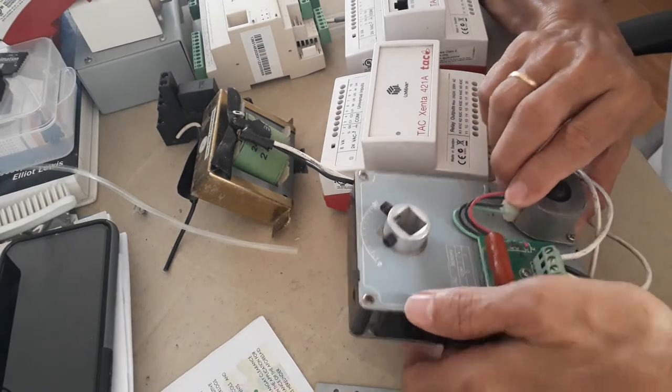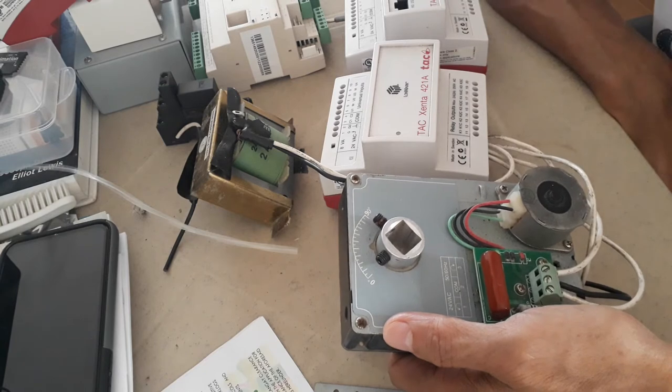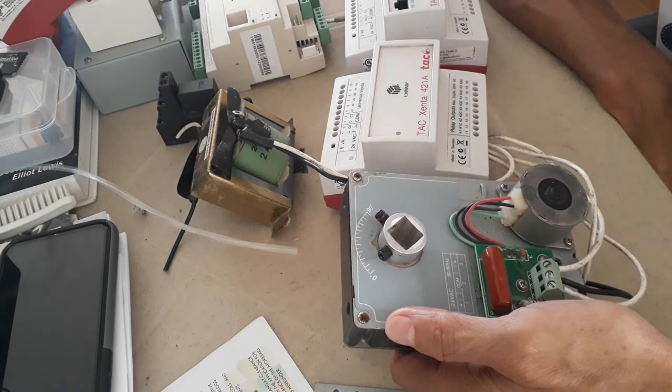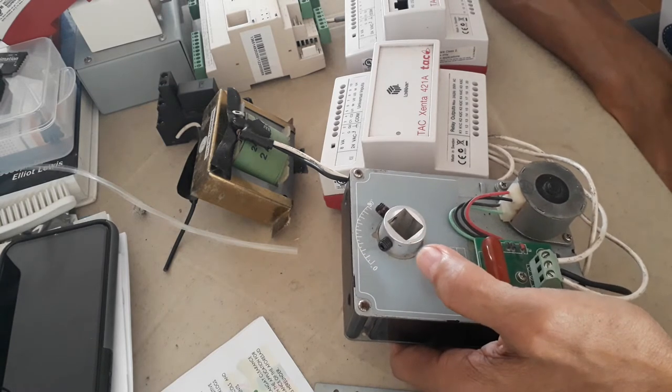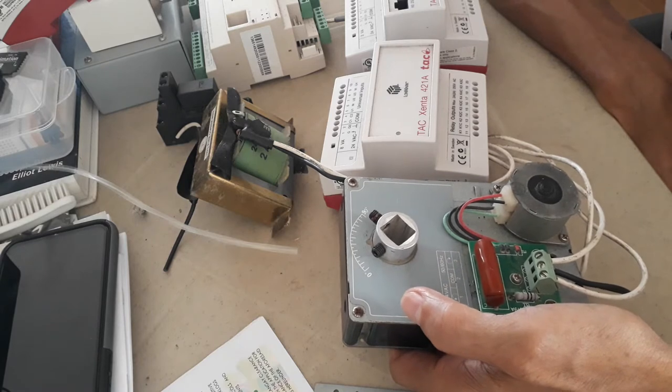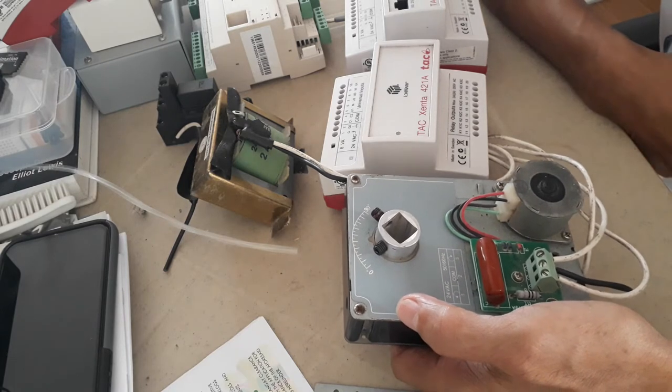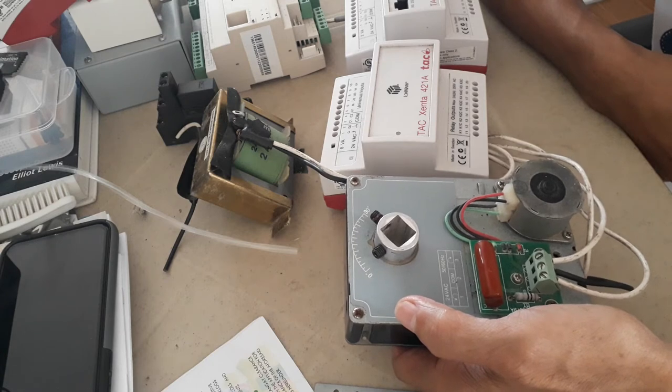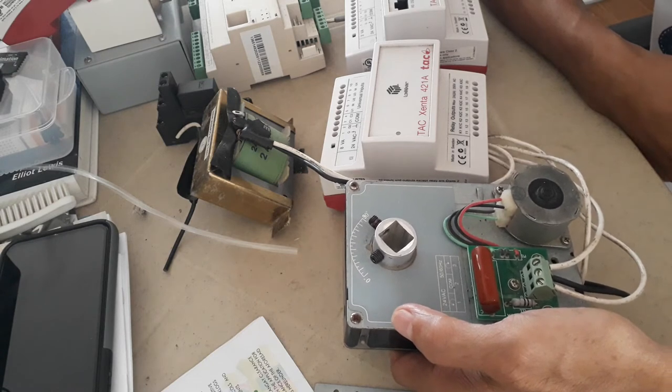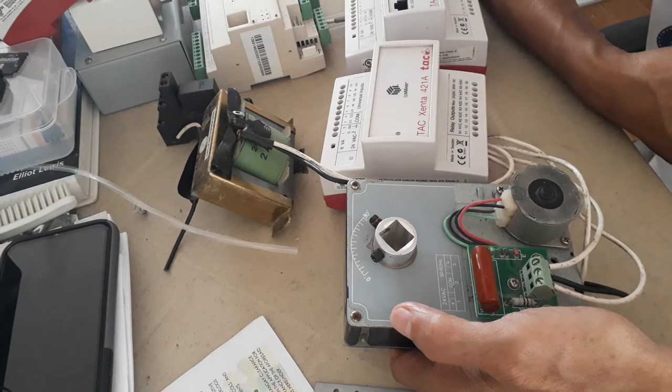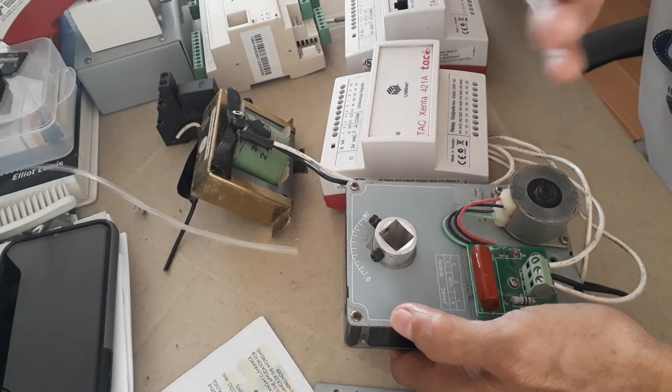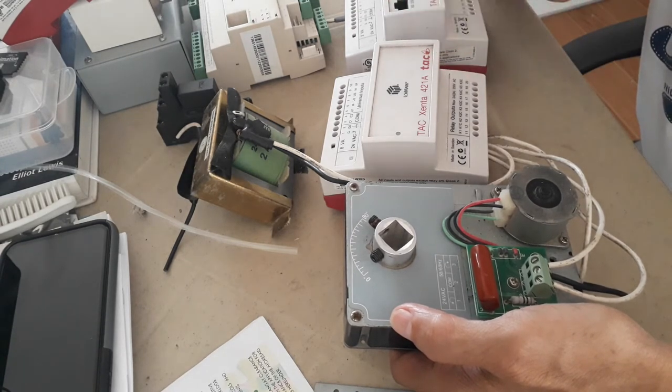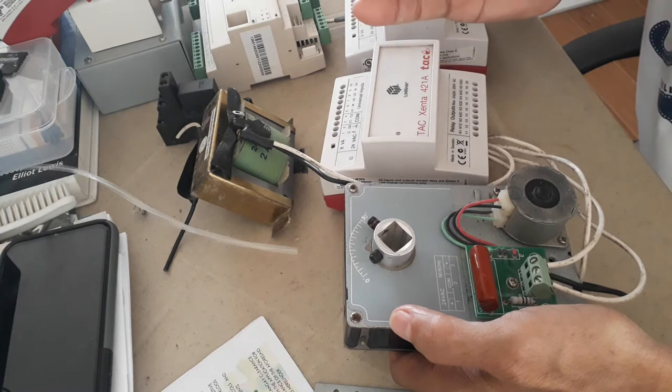What I have here is a damper actuator for variable air volume boxes. This damper actuator is wired to work on float point control or three position control. When you say float or three point position control, it is on or open, stop, close.